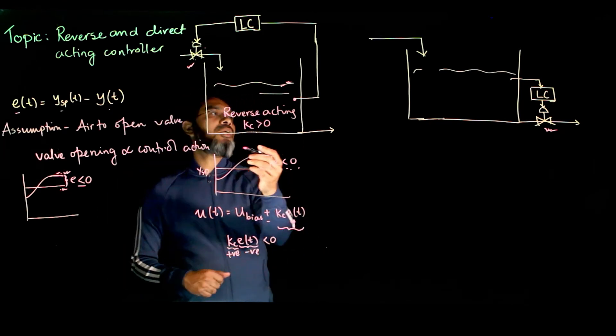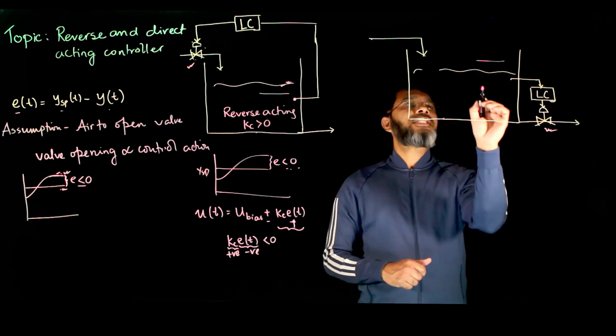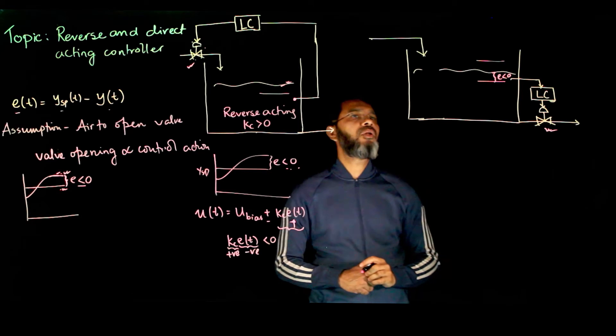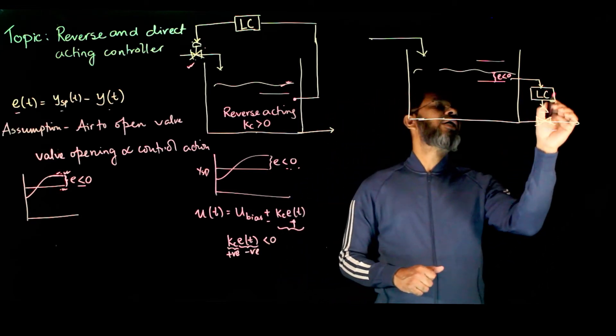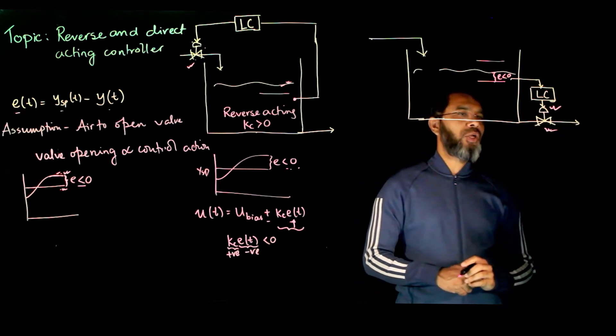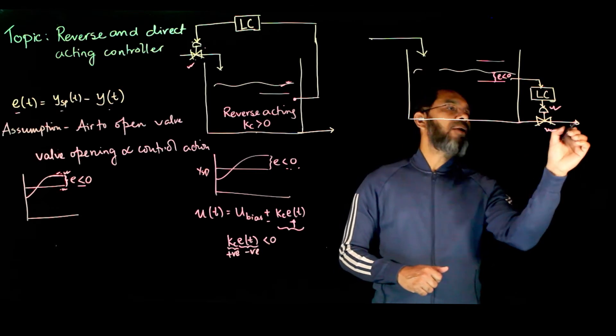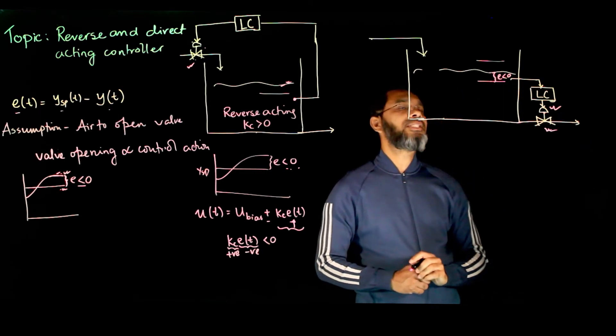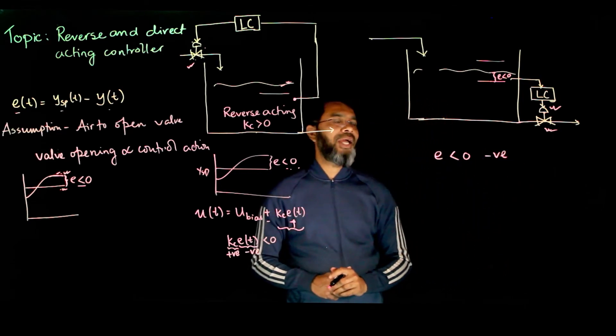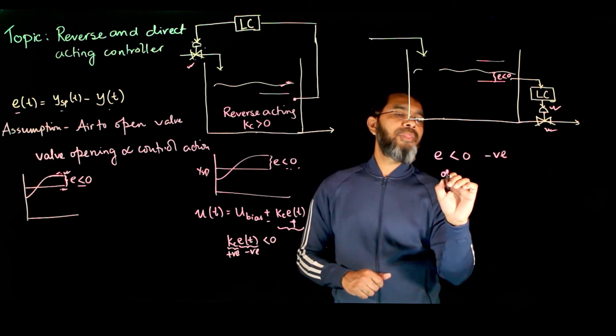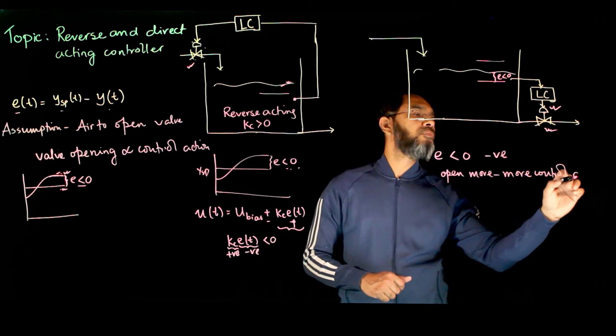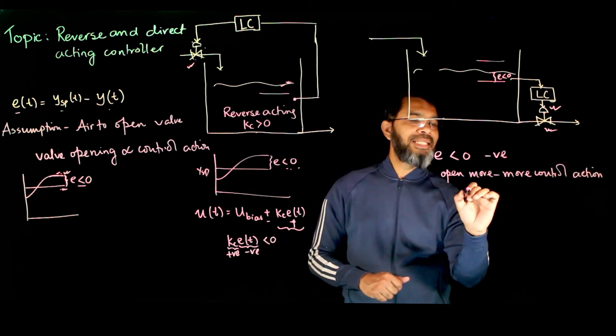Now compare with the outlet flow case. If the desired value is lower than the current value, the error is negative — the current value exceeded the desired value. In that case, you need to open the valve more, increasing the control action to drain more water so that the level comes back to the desired value. This is what is called direct acting.